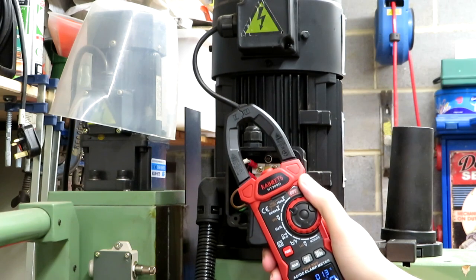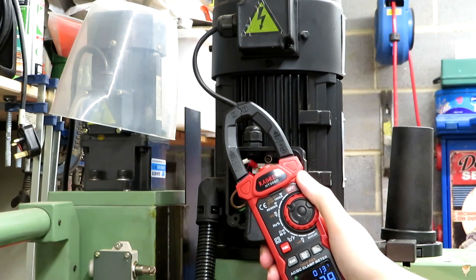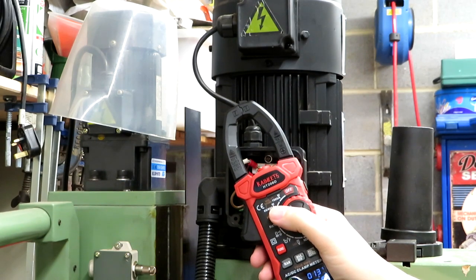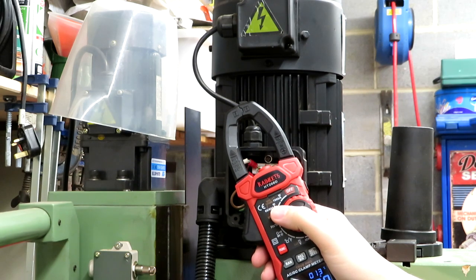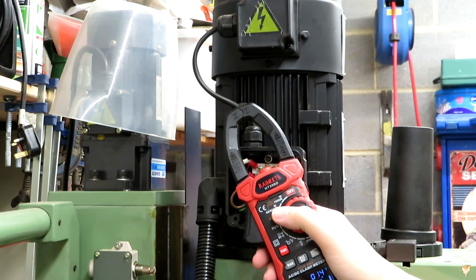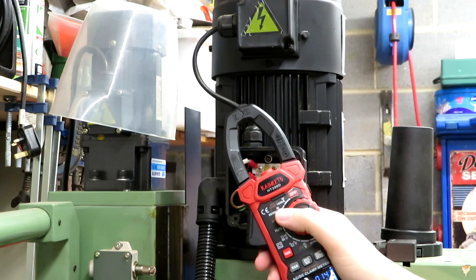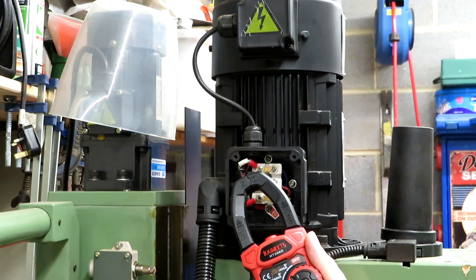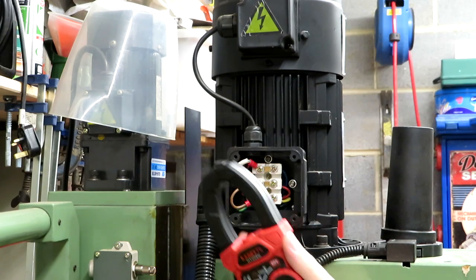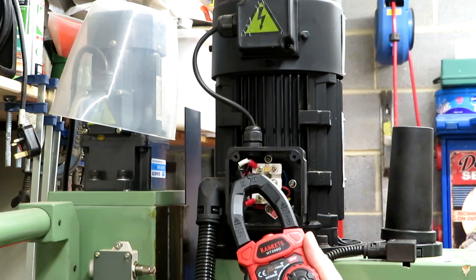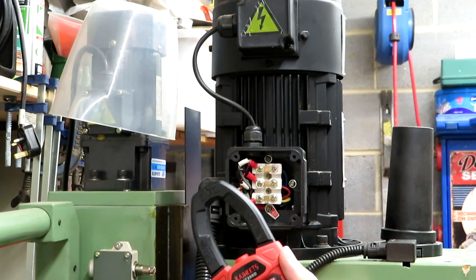So one of the main features of our KAIWEETS clamp meter is the fact that it does have this special VFD mode, which really just consists of a low pass filter. So basically it can filter out all that chopped up noise and display a true reading. And another advantage is that we don't actually have to disconnect the wire from the motor terminal here to make a reading. All we have to do is clip round this wire.